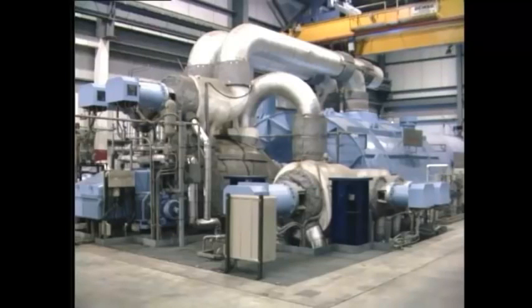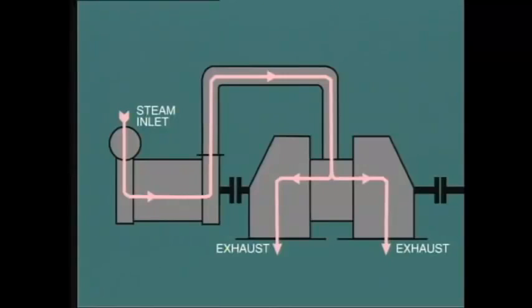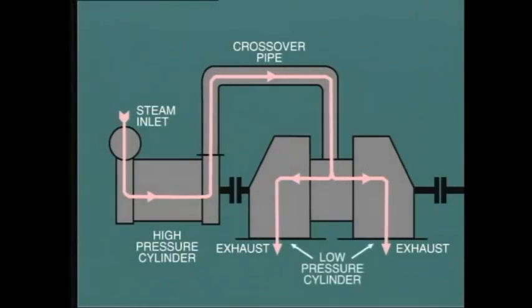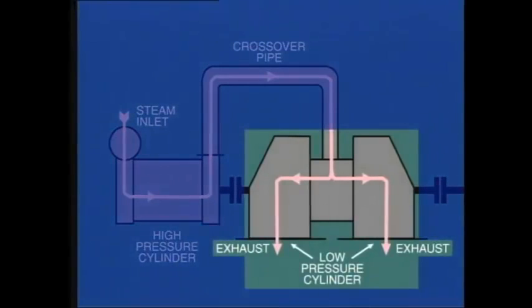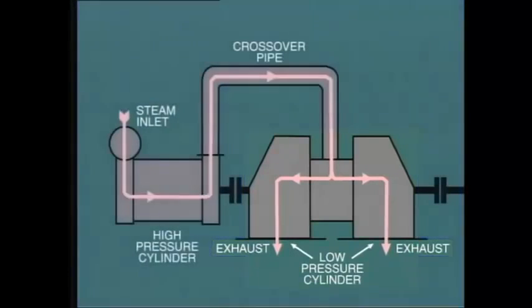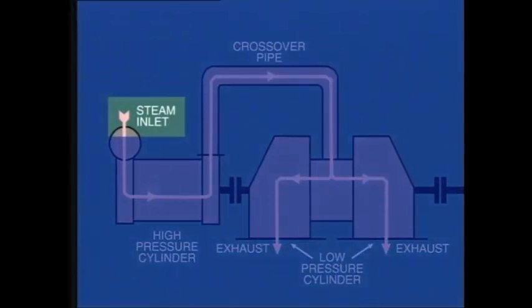To get over this problem, multi-cylinder arrangements are used, and let's look at some of these arrangements. Here we see a common arrangement of two cylinders which may be used for units of up to about 150 megawatts. Crossover pipes are used to connect the exhaust from the high-pressure cylinder to the inlet of the low-pressure cylinder. Most low-pressure cylinders are of the double flow type, where steam enters at the center and flows outwards in opposite directions. This provides some balance to the thrust and tends to keep the shaft centered. As the steam path of the high-pressure and low-pressure cylinders is in series, all of the control is carried out at the steam inlet admission valves at the high-pressure end.